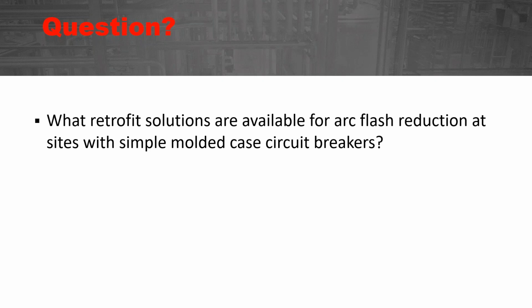It could also be an arc flash sensor, like a light sensor or pressure sensor, that could then help reduce the arc flash incident energy by changing the duration of the time for a circuit breaker to operate. You can even change the settings on the circuit breaker. So if it's set to 10 times instantaneous, you can reduce it to 4 or 6, as long as you don't start tripping breakers on inrush. That could also be an option.